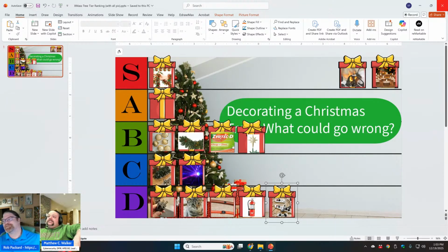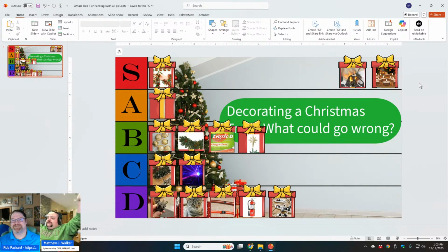So this is also something we see with the use-related risk analysis, is that there's not always a tremendous amount of things kind of in the middle. It either gravitates towards one end or the other. Either everything kills everybody, or it really can't hurt you at all.